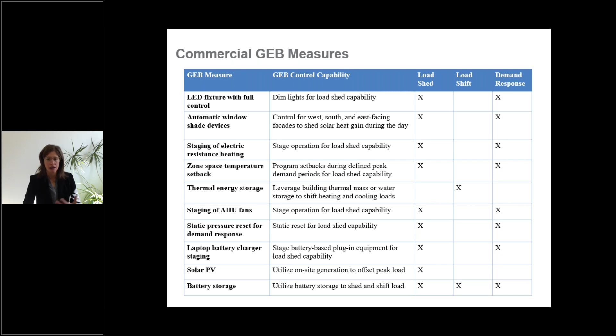In summary, we can leverage existing equipment in the building. Some of these technologies may or may not be smart—you can do manual controls, or you might have technologies that communicate with an intelligent control platform or building automation system. These may offer one or two-way communication with the grid, and we'll likely see more such technologies on the market. Building managers can control individual equipment or leverage software solutions that optimize multiple end-use systems. Flexibility can be provided through response to specific demand response events shared by the utility, or building owners can continually manage demand on their own, which provides more financial incentive through reduced demand charges and overall energy use.